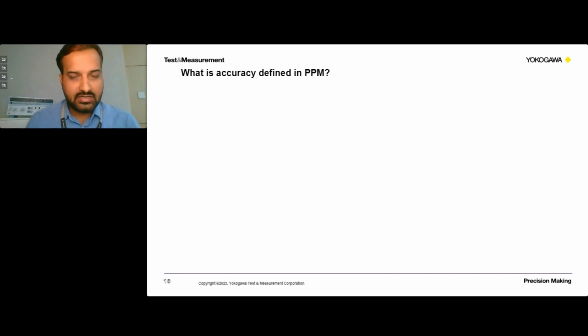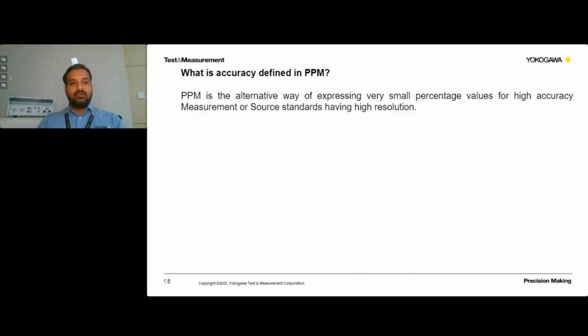And one more term which we come across when we talk about calibration is accuracy defined in parts per million. So what is parts per million? Any measurement value which is divided by a million is called parts per million. Usually it is also an alternative way of expressing accuracy for test and measurement instruments, or for the source and the source standards.